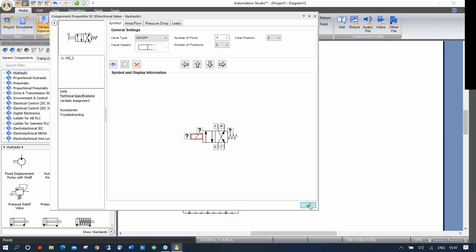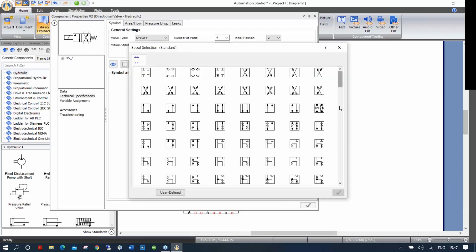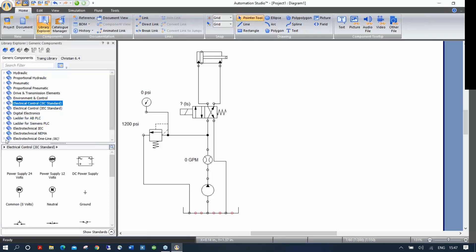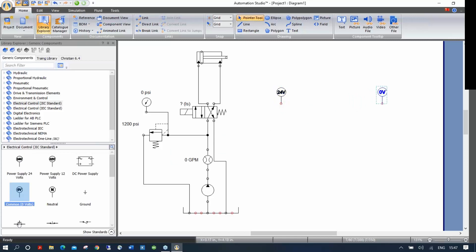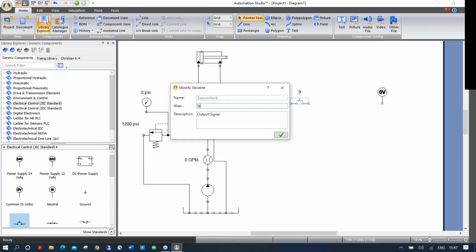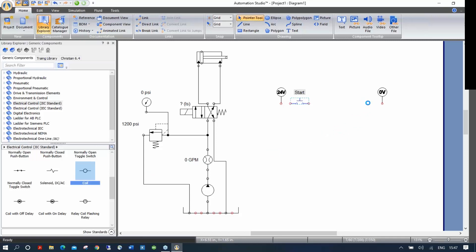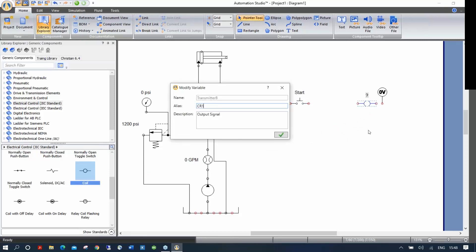In the same circuit, I'll go to Electrical Control (JIC Standard) and drag a 24-volt source, a 0-volt reference, a normally-open push button (which I'll label 'start'), and a relay which I'll name CR1. The software asks for a name when you drop the relay — you can put any name you want. Then I'll add a normally-open contact; the software automatically asks which relay it belongs to. I filter for 'C,' see CR1, and double-click to assign it.